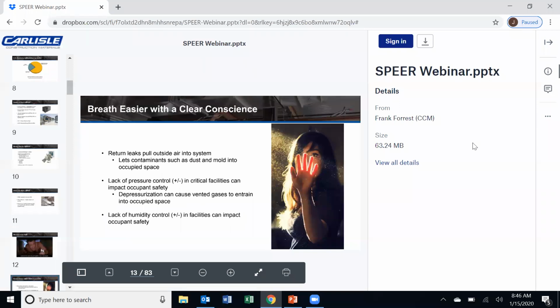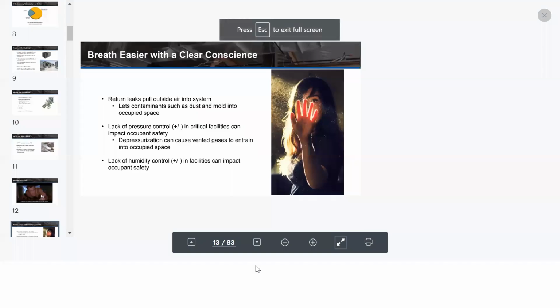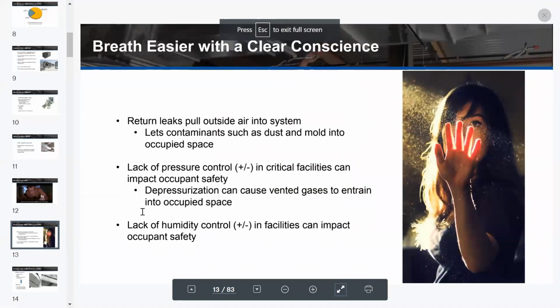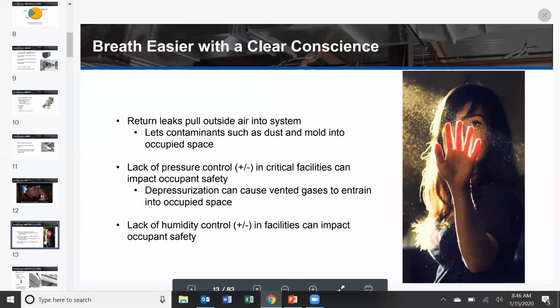All right, so when we're talking about breathing easier with a clear conscience, return leaks, we all know, can pull outside air, hot in the summer, cold in the winter, into the duct system, reducing both your efficiency and your capacity. Leaks in the return ductwork draw air into the building from crawl spaces, garages, attics, and above-ceiling grids, bringing with it dust, mold spores, insulation fibers, and any other contaminants that are up there.